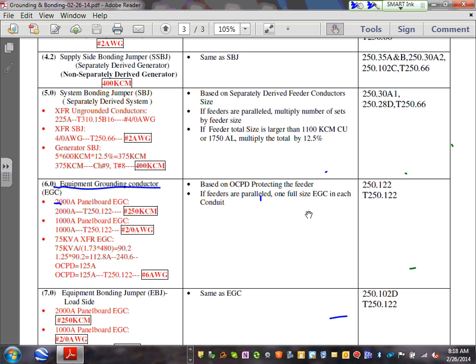How do you size it? You take 2000 amp, take it to 250.122, and that will get you 1 conductor, 250 kcmil, in each and every one of these conduits. Does it make sense? So that's how you size the 2000 amp equipment conductor. So there will be 5, one in each one of these conduits.